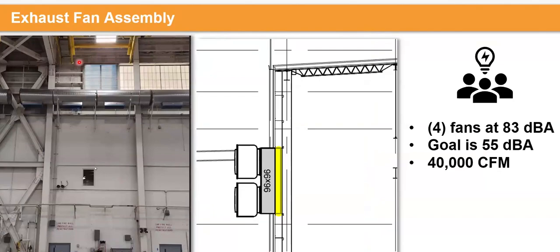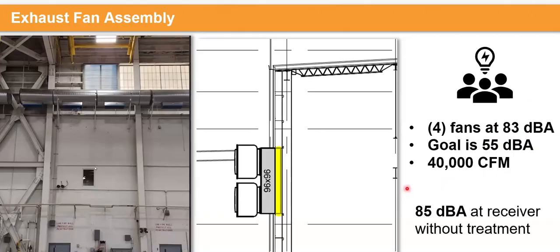Another job did come in for a high secret level military base where they had these openings on the side on the wall and they wanted to exhaust 40,000 CFM fans. So they decided 40,000. They went for four mushroom fans, each one at 83 dBA. So adding all of that up, these would be operating at 89 dBA. What was their goal? To get to 55 dBA for any worker that was standing right here and working right underneath this system. We used our acoustic analysis to determine that with the distance deductions, they would be at about 85 dBA with all these fans running at 100%.